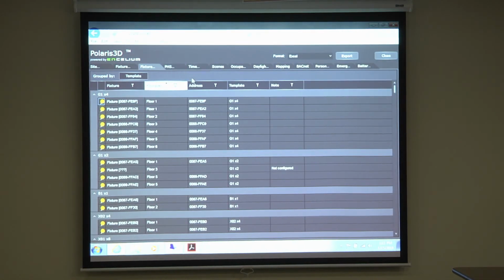Until it's full. But it's going to keep changing because if they're not harvesting, they're going to start dimming as soon as it sees sunlight. Let's do it at nighttime, probably, when there's no sunlight. You would have to do it at night, when I wouldn't have people in the building. I want to go to master control and trigger everything on. Yeah, exactly. That would give you accurate numbers.